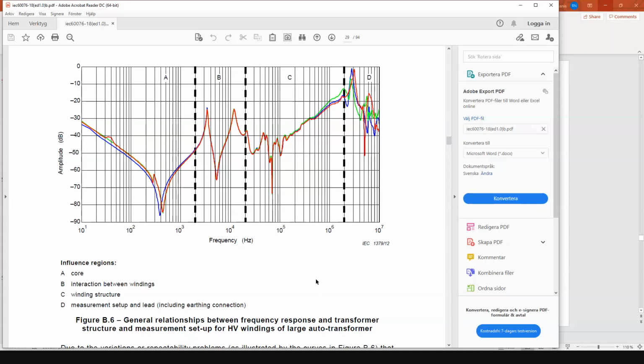Right, and the last question we are having is, what's the frequency of doing SFRA for a transformer? Every year, or just after maintenance? Well, if you do transformer maintenance and you disassemble something and then disconnect the windings or change bushings or things like that, then after that I would certainly advise to do that. But otherwise, if the transformer is not subjected to any faults or any overhauls, then it could be several years between two tests. So it all depends on the owner's strategy.